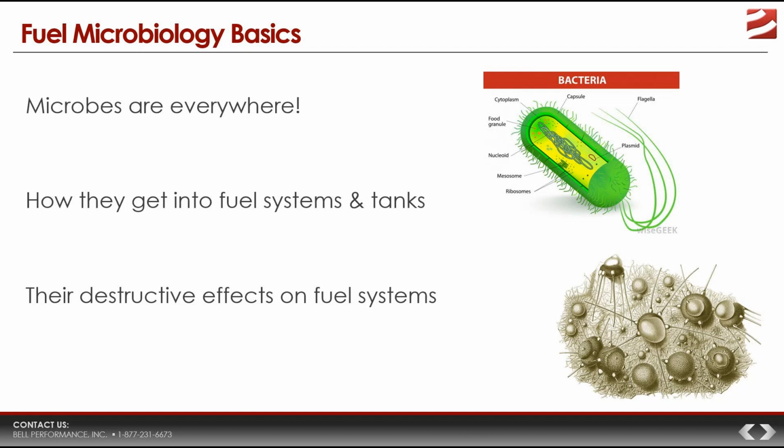When it does that, it can actually get trapped in pockets, especially if it happens around biofilm, which then you get a localized area of a high concentration of oxygen, which leads to the formation of things like carbonic acid, which is very corrosive to metal. And you can get not only a localized high concentration of oxygen, you can get the same for carbon dioxide as well. So again, this is the kind of thing that you could spend a lot of time getting way down into the details here. But I think you get the picture of what we're talking about.